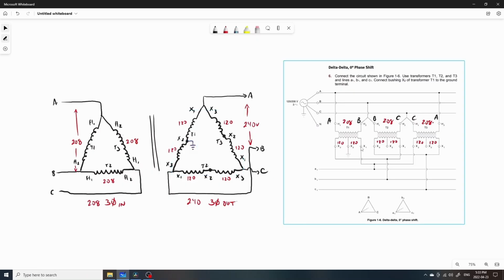The wiring here: X1 is coming down and tying into A, so X1 goes to A. Then X3 goes to B - remember, A to B, B to C, C back to A. On the second transformer, X1 goes to B, and X3 goes to line C. Then on the final transformer 3, we have X1 to C, which is seen right here.